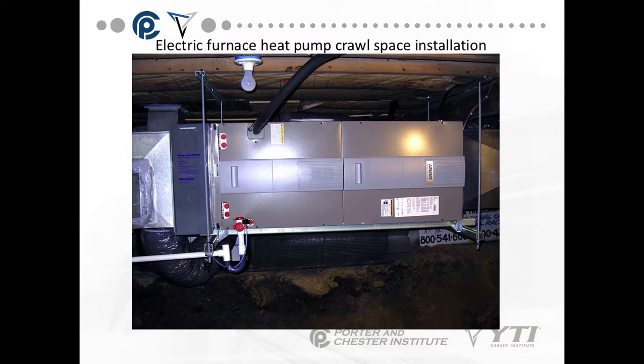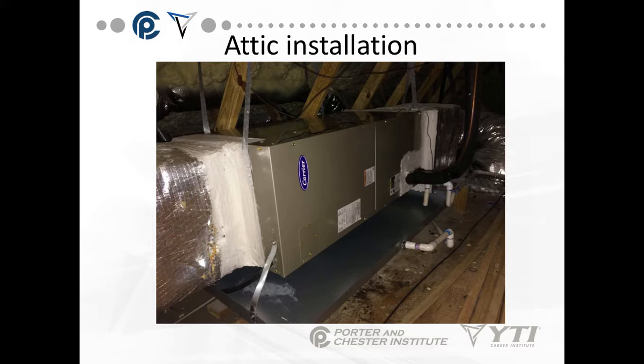This is an example of a crawl space installation. Again, remember we said it can be suspended. You still have your condensate lines. And this is a horizontal installation, but it's not on the dirt floor of the crawl space. An attic installation always requires an overflow drain pan with an emergency overflow. The reason for this is so that if the condensate gets clogged up here, it will go into the drain pan and won't destroy the ceilings. Notice how the ductwork has mastic on it, and everything has been sealed, even around the refrigeration line, so there's no air leakage.